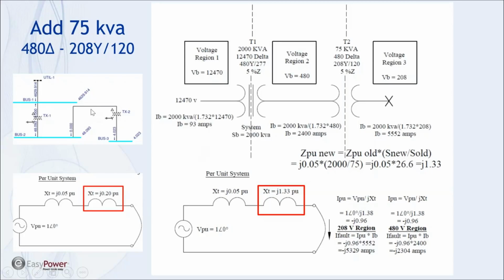I also took the same thing here and put it into EasyPower. Now here was a number, and I worked with this trying to explain why, but this is quite a bit smaller. I only got 4,000 amps compared to my 5,329 here. Anyway, still less than 5,000 amps. So that's the 75 kVA. Hopefully that gives you some insight into how smaller transformers impact available fault current in electrical distribution systems.